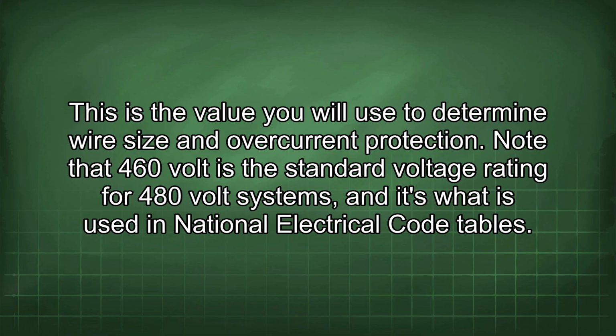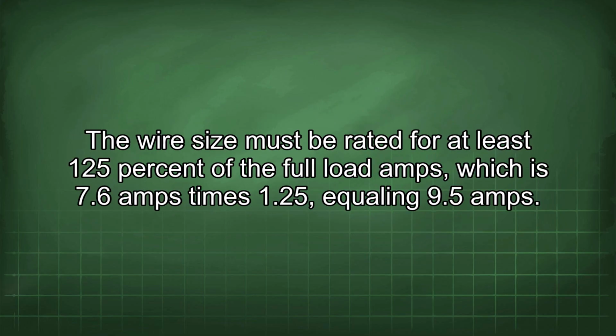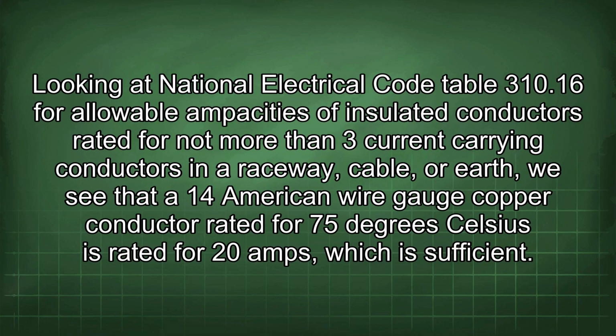Note that 460 volt is the standard voltage rating for 480 volt systems, and it's what is used in National Electrical Code tables. The wire size must be rated for at least 125% of the full load amps, which is 7.6 amps times 1.25, equaling 9.5 amps. Looking at National Electrical Code Table 310.16 for allowable ampacities of insulated conductors rated for not more than 3 current-carrying conductors in a raceway, cable, or earth, we see that a 14 American wire gauge copper conductor rated for 75 degrees Celsius is rated for 20 amps, which is sufficient.